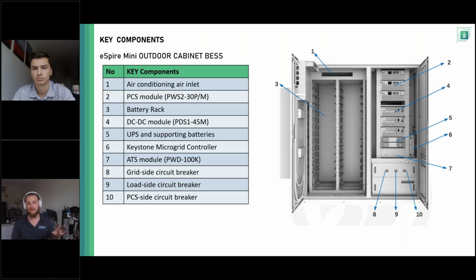This has an automatic transfer switch built in to go from grid following to grid forming mode and vice versa. It is a static transfer switch, so the switching time is about 30 to 40 milliseconds. It's not a UPS system, like the less than 10 milliseconds that's required for some data center operations or hospital scenarios, but we can pair it with a UPS that would handle, say, the first 5 to 10 minutes of those critical functions, so that the inverter can then form the grid and we can switch that battery power back over. And it's got all your load side, grid side, and inverter side circuit breakers here as well, so that we're not over amperage.